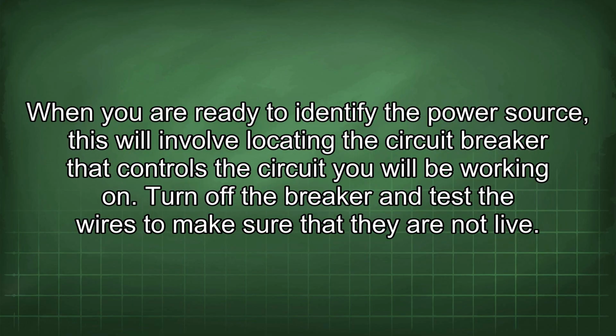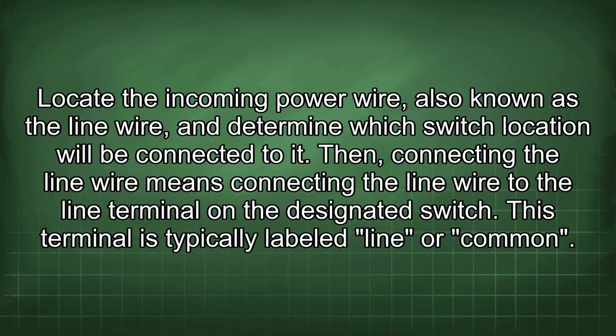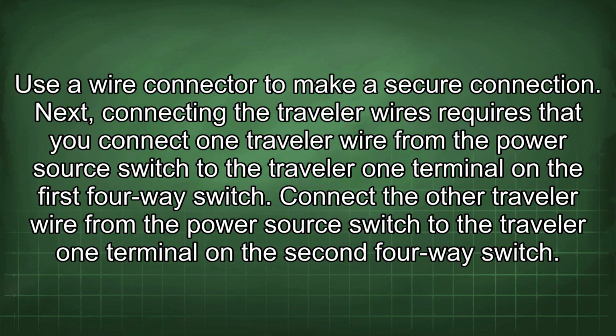When you are ready to identify the power source, this will involve locating the circuit breaker that controls the circuit you will be working on. Turn off the breaker and test the wires to make sure that they are not live. Locate the incoming power wire, also known as the line wire, and determine which switch location will be connected to it. Then, connecting the line wire means connecting the line wire to the line terminal on the designated switch. This terminal is typically labeled line or common. Use a wire connector to make a secure connection.